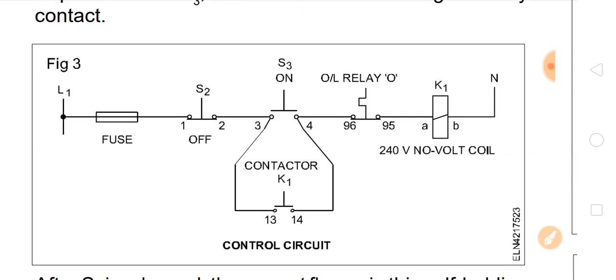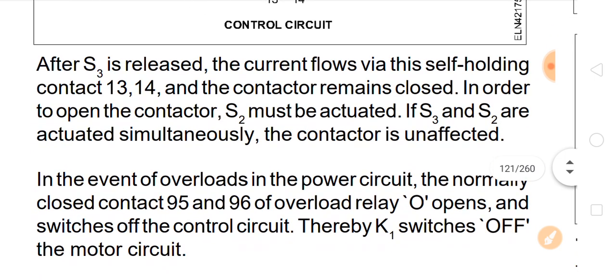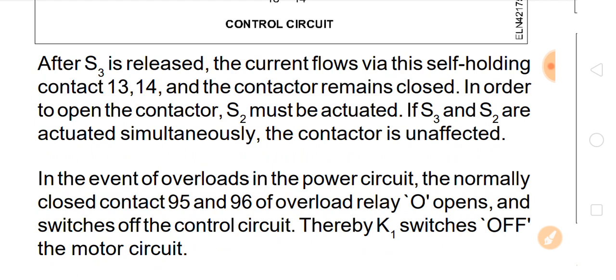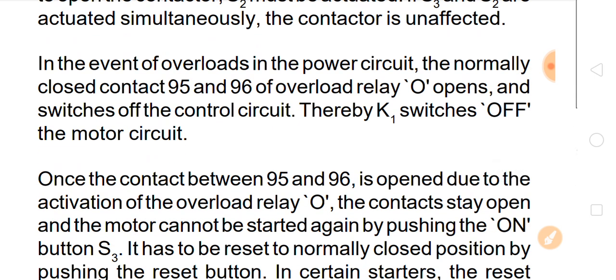The control circuit includes no-volt coil K1 neutral, overload relay contacts 96 and 95, S3 on button, and S2 off push button with fuses. After S3 is released, current flows via the self-holding contact 13 and 14, and the contactor remains closed. In order to open the contactor, S2 must be actuated. If S3 and S2 are actuated simultaneously, the contactor is unaffected. In the event of overload, the normally closed contact 95 and 96 of the overload relay opens and switches off the control circuit, thereby K1 switches off the motor circuit.